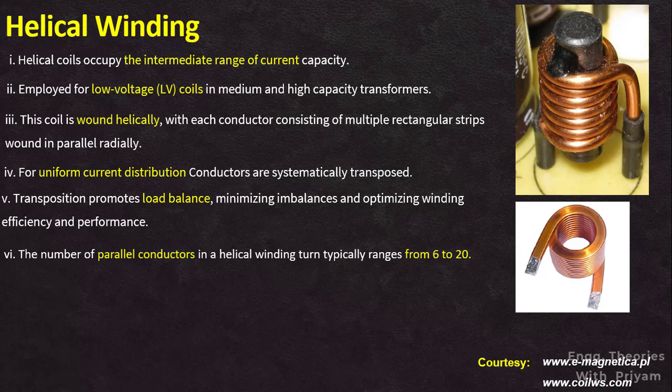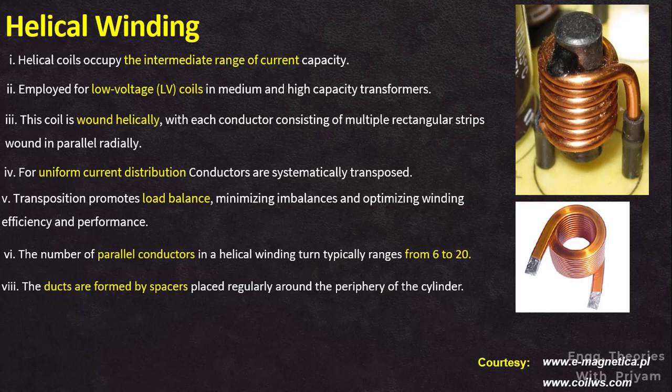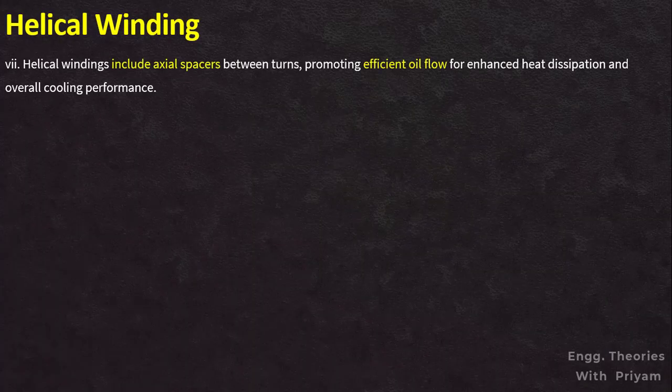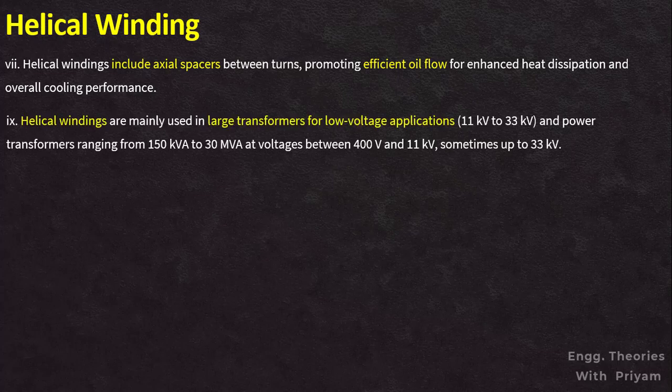The number of parallel conductors in a helical winding typically ranges from 6 to 20. Ducts are formed by spacers placed regularly around the periphery of the cylinder. Helical windings incorporate axial spacers placed between adjacent turns, which facilitate better oil flow within the winding, resulting in more efficient heat dissipation and enhanced cooling performance. Helical windings are mainly used in large transformers for low-voltage applications of 11 kV to 33 kV, and power transformers ranging from 150 kVA to 30 MVA at voltages between 400 volts and 11 kV, sometimes up to 33 kV.